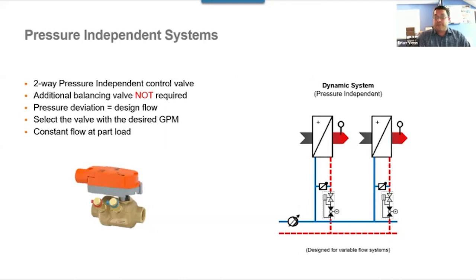This is where the verification now starts to come in. So for balancers, the traditional, well, I got to go out there and balance and set the valve. It just changes a little bit and possibly pivots. And we really become a verification of both installation and manufacturer delivery. So in that regard, the balancer, to your point, is still required. But also to your point, the control valve now is going to work a little bit like a VAV. And if we change static pressure in the system or the pump, then we may not have to go back in the time-consuming manner and rebalance everything. And I think that was your point earlier, Bob. Yes, it is.